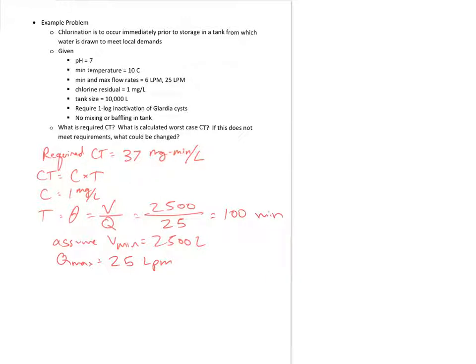Now, with my time at 100 minutes and my concentration at 1 milligram per liter, my CT would be 100 milligram-minutes per liter, which is greater than my required CT. But before I do that, I recognize it says no mixing or baffling in the tank. So what happens if water comes into the tank and doesn't spend the entire residence time in the tank?